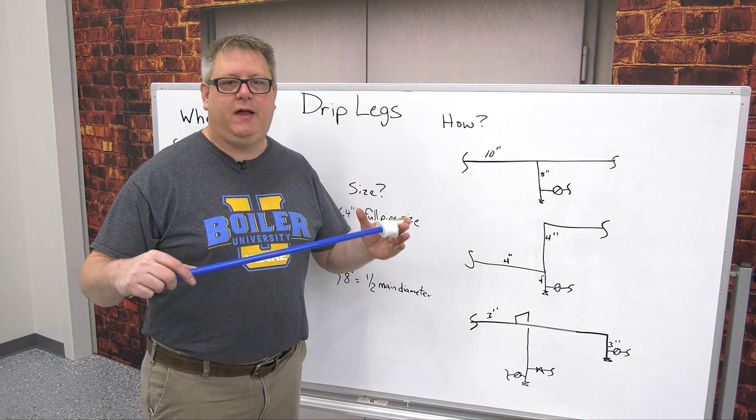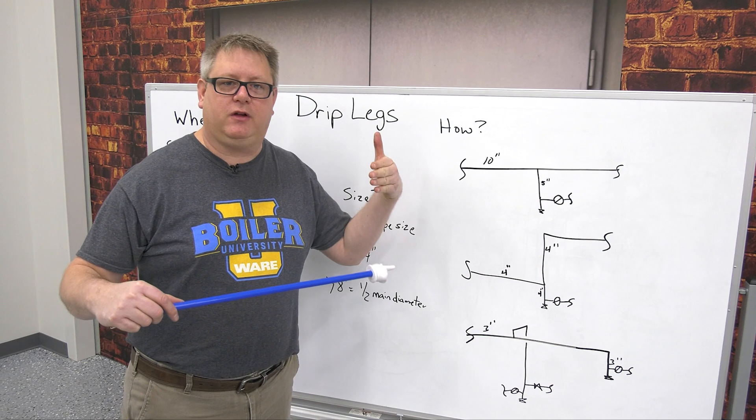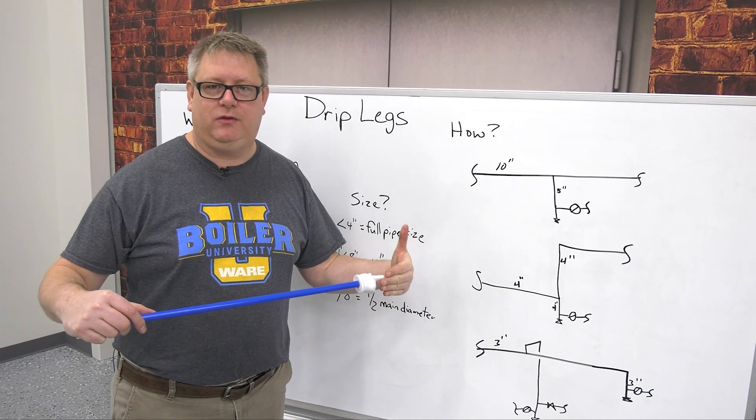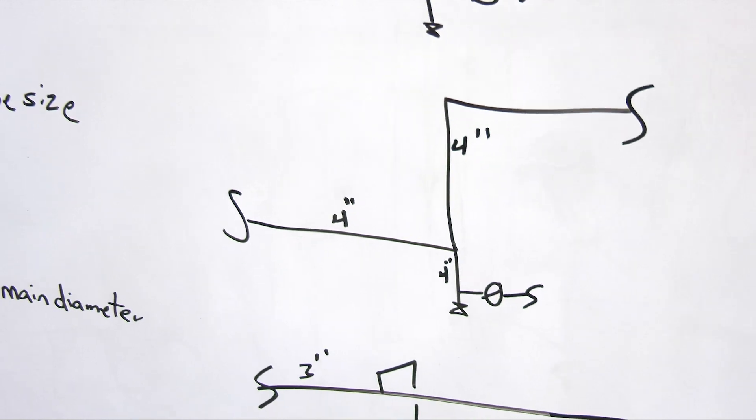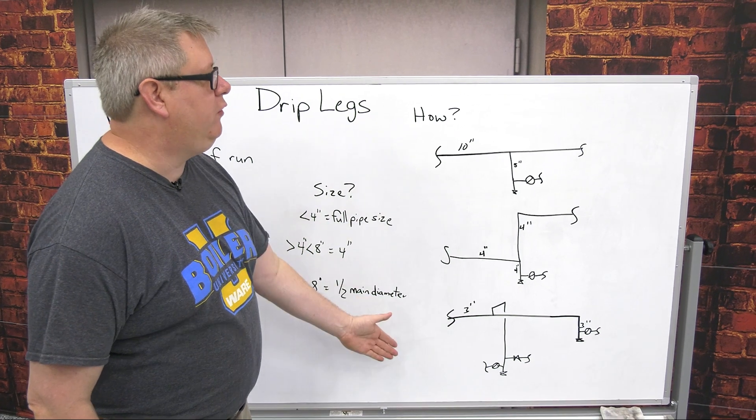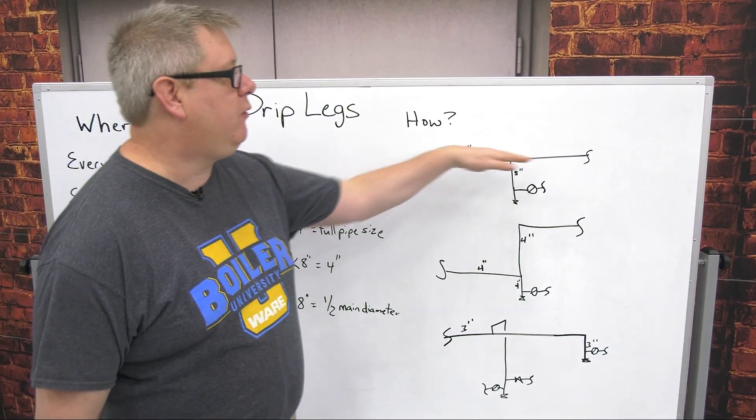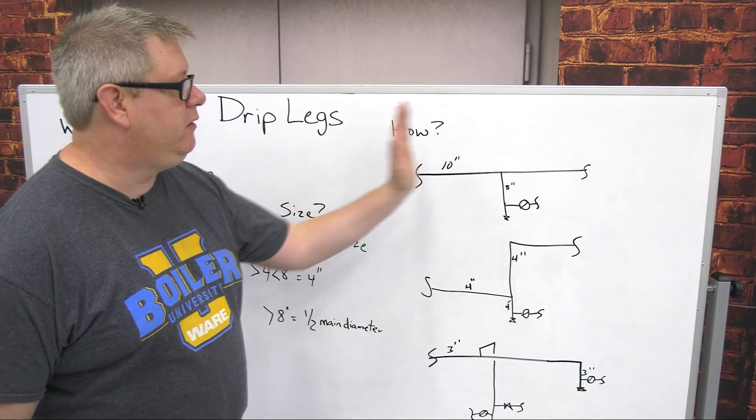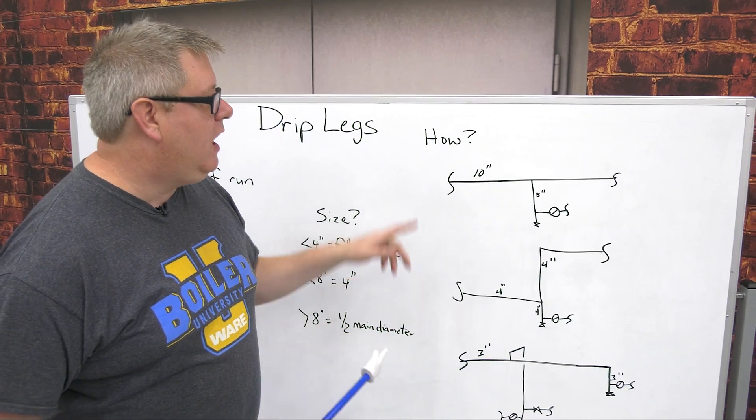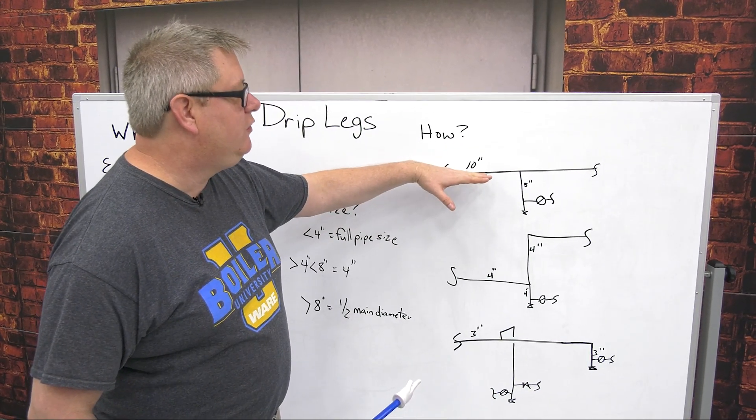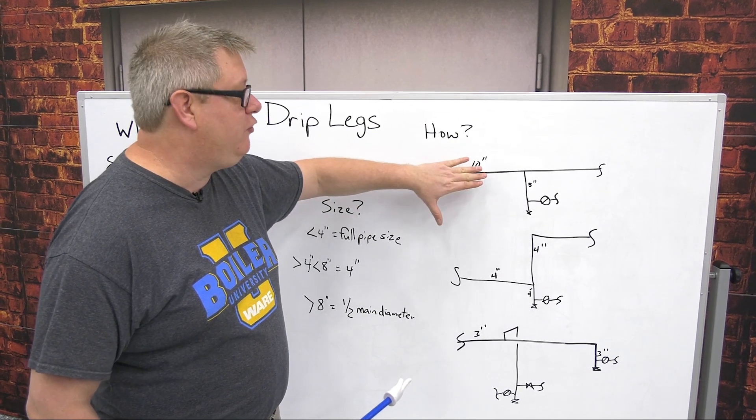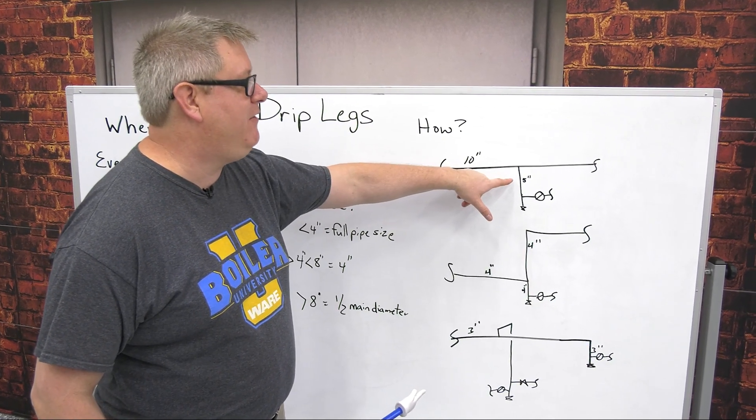We've looked at some drip legs. We've talked about specifically where drip legs need to be in the system, and today we're going to look at how those drip legs are going to look for different applications in the system. So how are we going to install the drip legs? If I've got a horizontal run, one of those 200 foot interval portions, I'm going to look at my main line size. In this case it's 10 inch.